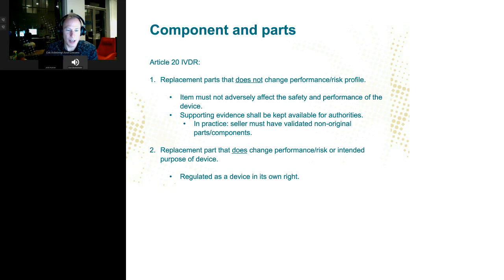Very important. If you have a replacement part that does extra things, so it changes the intended purpose, then your part is regulated as a device in its own right. Congratulations. The part needs to be CE marked as an IVD under the IVD regulation. So this is another regulatory category of, let's say, accessory-like medical devices, but then being replacement parts that extend performance of the device. And this is a big problem in a market where, let's say, you're in lab instrumentation, where you develop new parts that do not only replace existing functionality, but also add additional functionality. This is critical for you to understand.